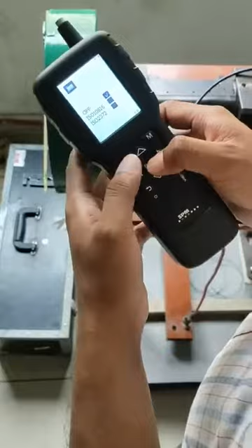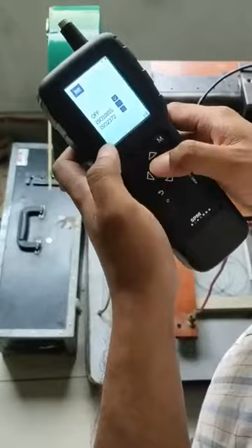This is the vibration screen with ISO standards. If you want to follow ISO standards, you can select them as per your request. This instrument has only 2 options, ISO 10816 and ISO 2372. If you don't want to use ISO standards, you can select the off option also.